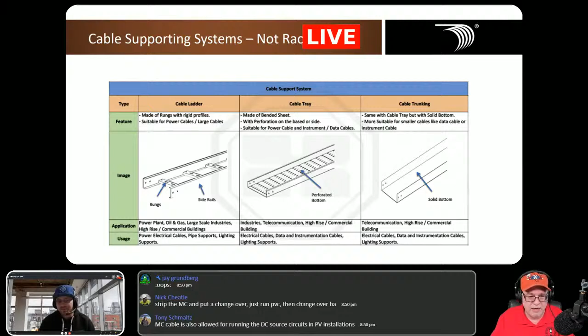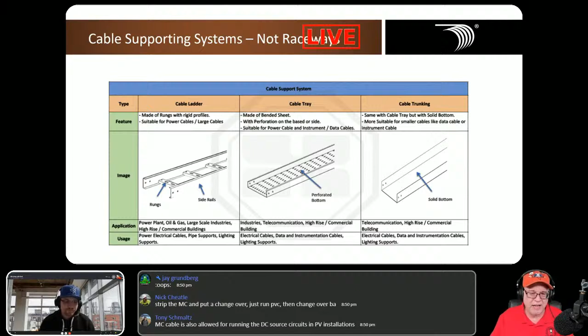Again, an advantage of MC is that PVC jacketed MC is readily available in most places, and it makes for a nice, easy transition, whereas tray cable can't come into a building unless it's inside of a raceway, in a cable tray, on messengers, or direct buried. So there are some limitations with tray cable that you don't have with MC cable.